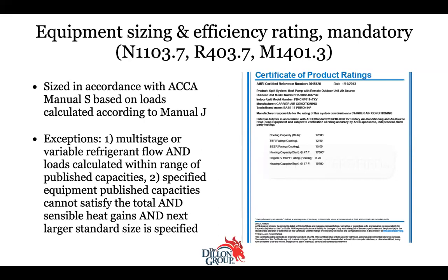So, the funny thing is, it seems like HVAC contractors don't do this. Because what I see a lot of is they use the AHRI certificate. And they say, here's the capacity of the equipment. And if they do have a load calculation done, they match it that way. They size it based on the AHRI certificate, or they select it based on the AHRI certificate. So I'm going to share some information about AHRI. I did a presentation similar to this in 2008, and people seemed to be stunned. So get ready.